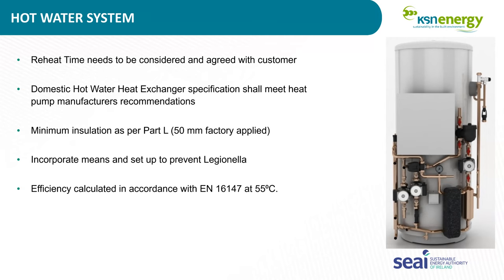They have to try and calculate the size of the coil or heat exchanger in the cylinder to see that it's sufficient. Whereas typically when they see a manufacturer's indoor and outdoor unit, they know it's sized correctly because the manufacturers sell it sized properly. The insulation has to be sufficient on it. So, as a minimum, it has to be Part L compliant, so a minimum of 50 mil of factory insulation has to be on it.